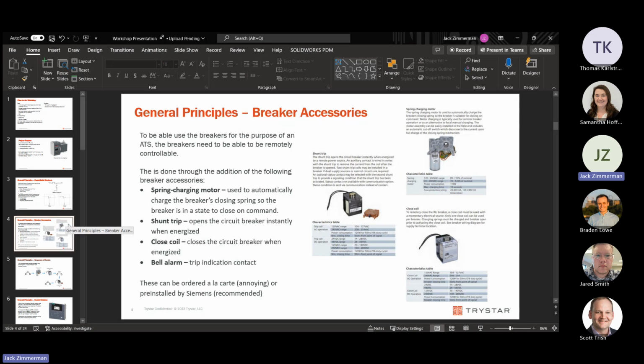So I looked at the characteristics table for the close coil and the shunt trip. Are those numbers copy-pasted from a vendor brochure? Yes, so this is all from a reference - all of the unnamed references you'll see are from the Siemens WL breaker manual that we use. And when you made the choice, it was based on those characteristics.